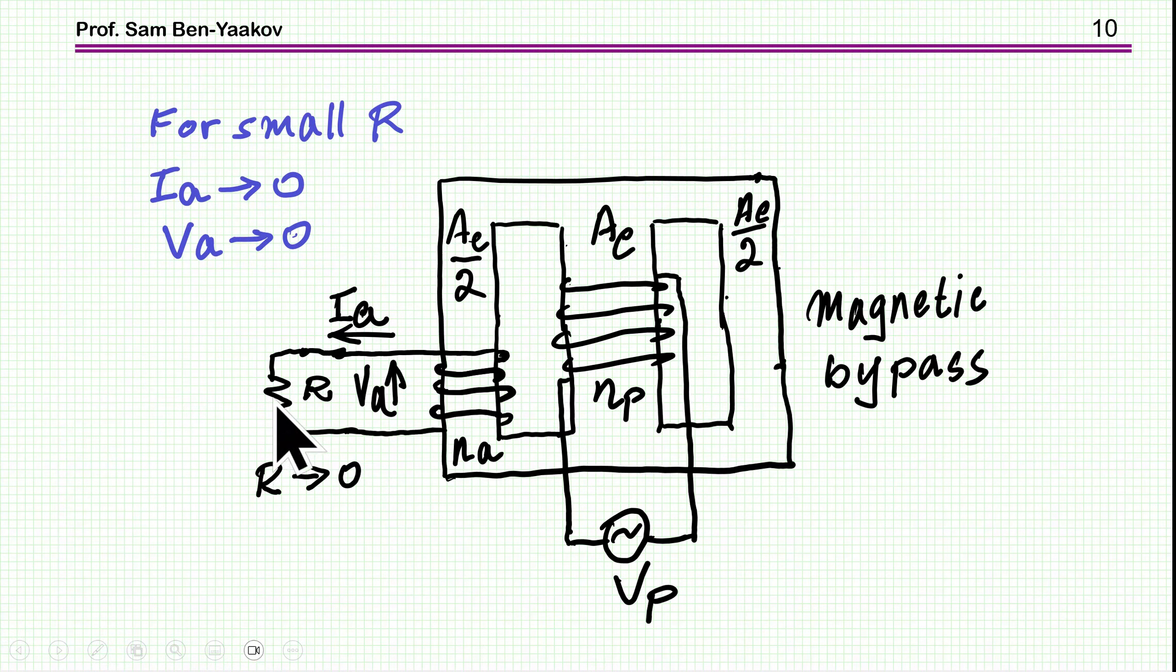So if we have this short, this is the case of the short, then we have an uneven distribution of the flux. And in this leg, then the flux will be much lower and the current will be also low. So this behavior is really different from a regular transformer, because if we have a transformer and we are shorting the output, we would expect a large current due to the short. Now, in this case, not so, because of the flux distribution or redistribution, I should say, that most of the flux is now passing through this magnetic bypass. And therefore, the voltage is low here and the current will be low.